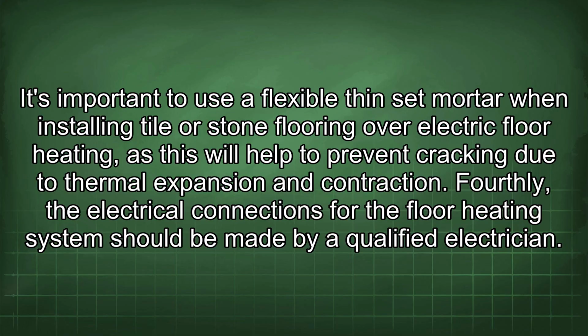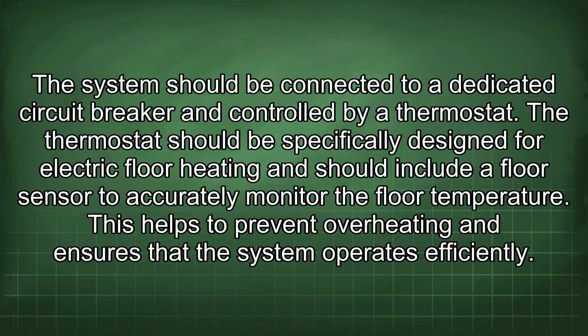Fourthly, the electrical connections for the floor heating system should be made by a qualified electrician. The system should be connected to a dedicated circuit breaker and controlled by a thermostat. The thermostat should be specifically designed for electric floor heating and should include a floor sensor to accurately monitor the floor temperature. This helps to prevent overheating and ensures that the system operates efficiently.